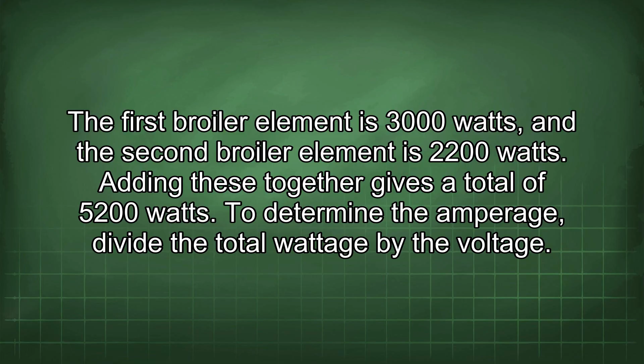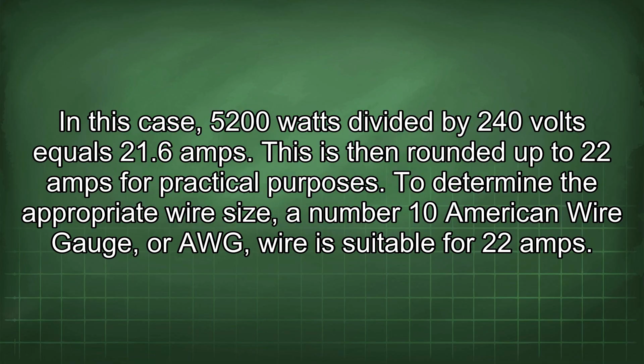To determine the amperage, divide the total wattage by the voltage. In this case, 5200 watts divided by 240 volts equals 21.6 amps. This is then rounded up to 22 amps for practical purposes. To determine the appropriate wire size, a number 10 American wire gauge, or AWG, wire is suitable for 22 amps.